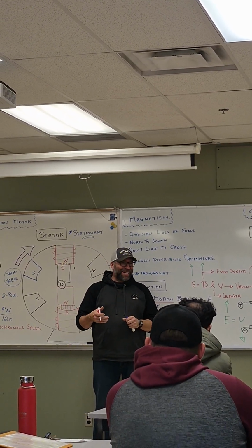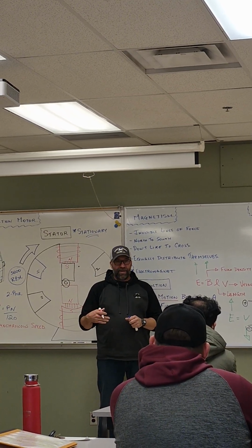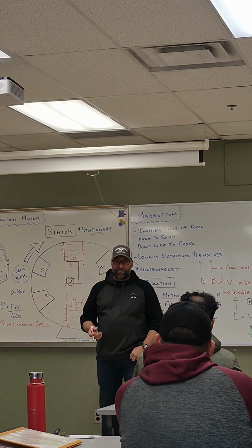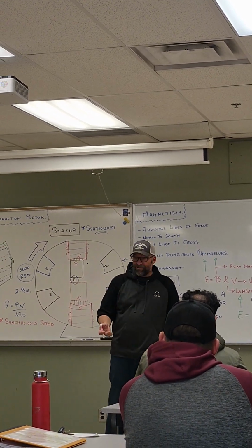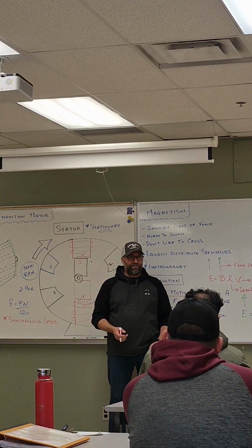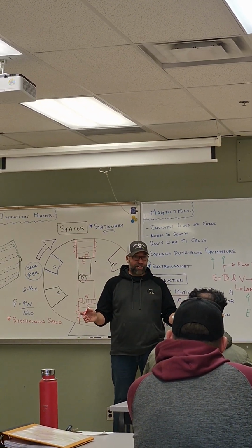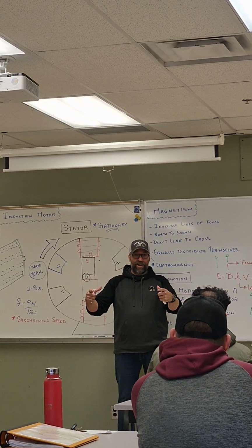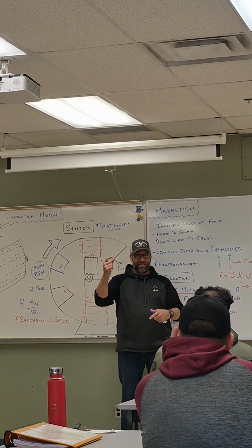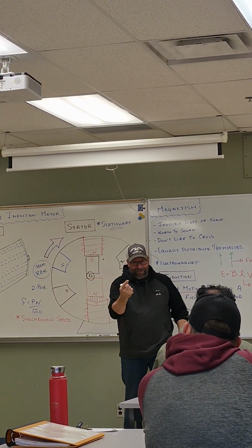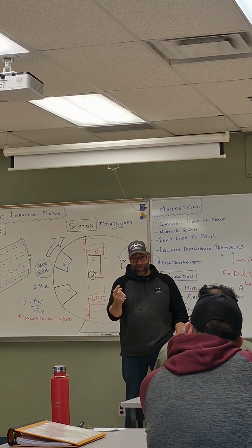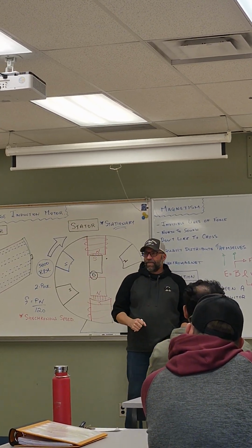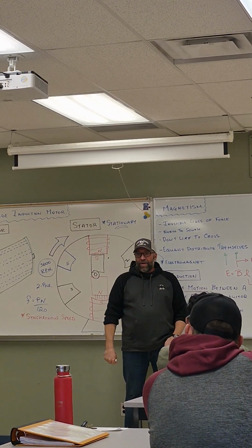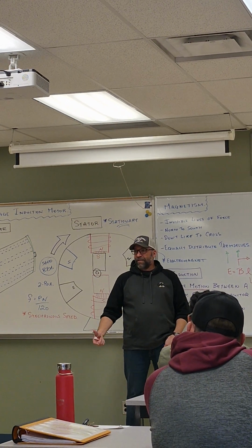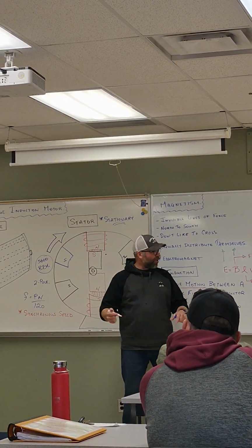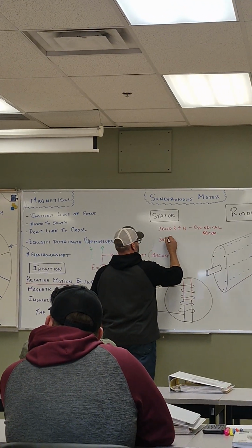But for low speed, which is actually a lot of the stuff we do, I'll give you an example, Peace Canyon Dam. I didn't mention that just because I thought it was cool. It actually is part of this little lesson. Peace Canyon Dam turns at 58 RPM. That's what the rotor turns. 58. 5.8. You could watch the nick on the shaft go by. The shaft is 14 inches in diameter. That's between where the water turns it and where the rotor spins. It's this big around. You can watch a nick on the shaft go by. It's like, yeah, that's a little more than a second to come around. 58 RPM. It also means it's like from here to that window in diameter. That's called a salient pole. Low speed, salient pole. So that's when you're down to like 58 RPM.